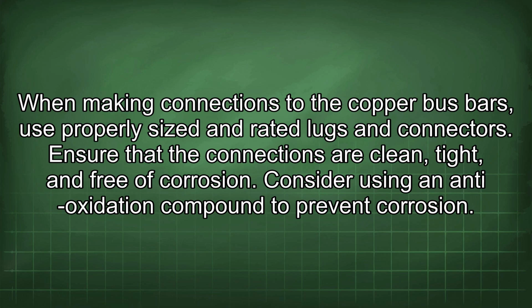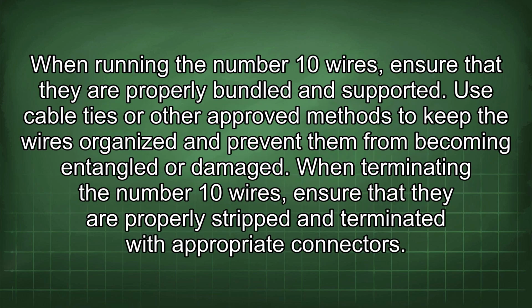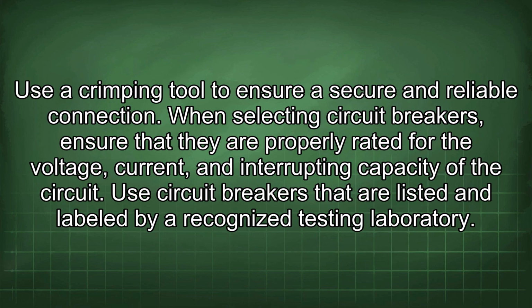When making connections to the copper bus bars, use properly sized and rated lugs and connectors. Ensure that the connections are clean, tight, and free of corrosion. Consider using an anti-oxidation compound to prevent corrosion. When running the number 10 wires, ensure that they are properly bundled and supported. Use cable ties or other approved methods to keep the wires organized and prevent them from becoming entangled or damaged. When terminating the number 10 wires, ensure that they are properly stripped and terminated with appropriate connectors. Use a crimping tool to ensure a secure and reliable connection.